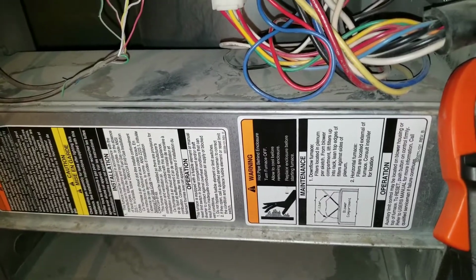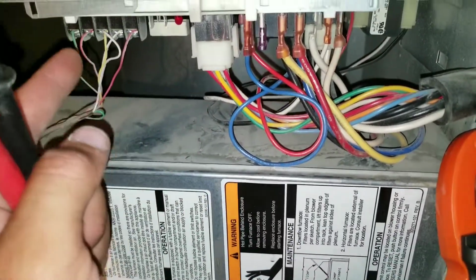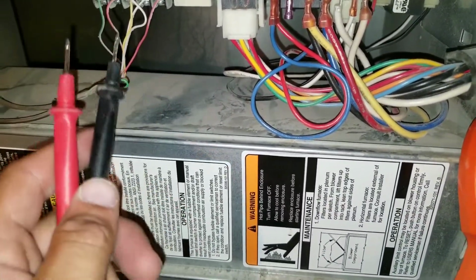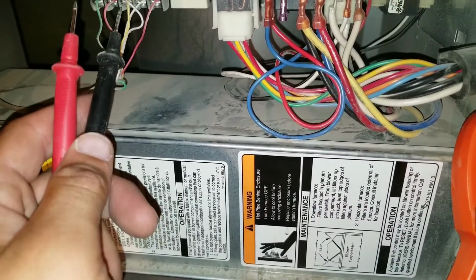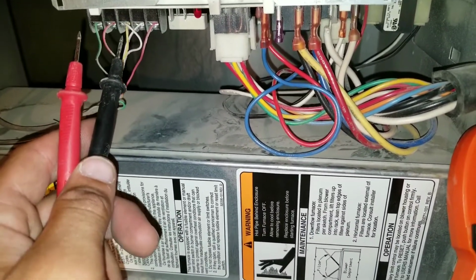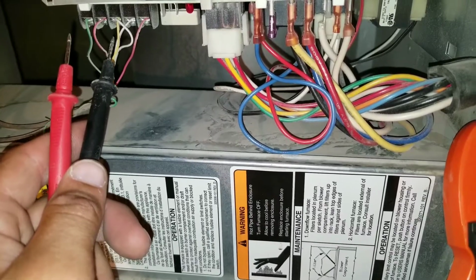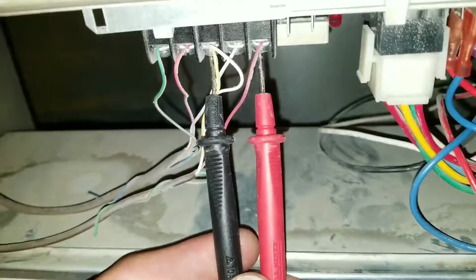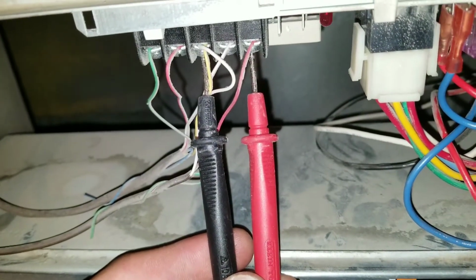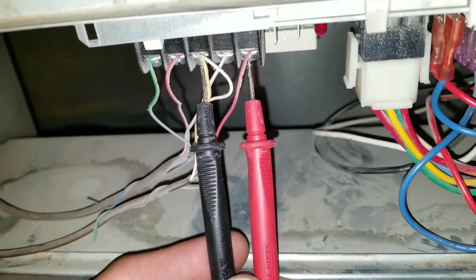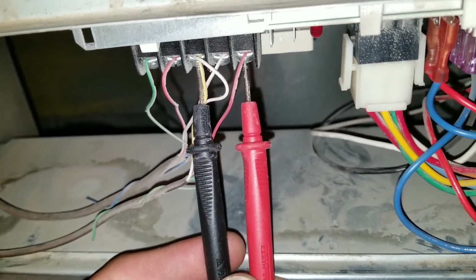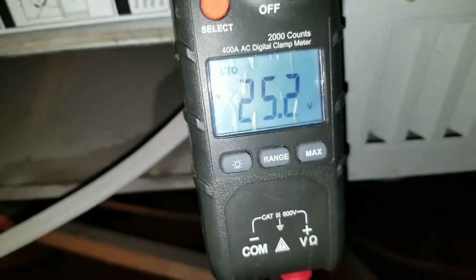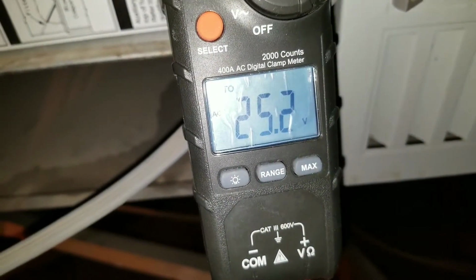It is running. And right now before I leave, I just want to check my voltage here on my common to my Y terminal, which is going to be for my condensing unit, and just make sure that we're getting the proper voltage there. So here I have one on my common, one terminal's on my Y terminal, which is my yellow wire. And here I do have a reading of 25 volts.